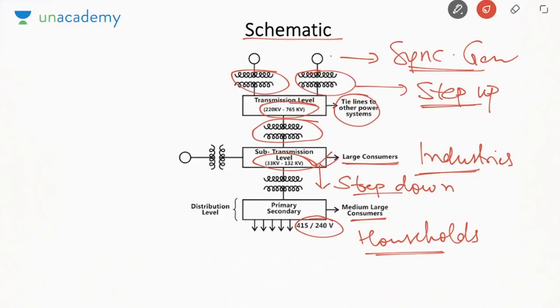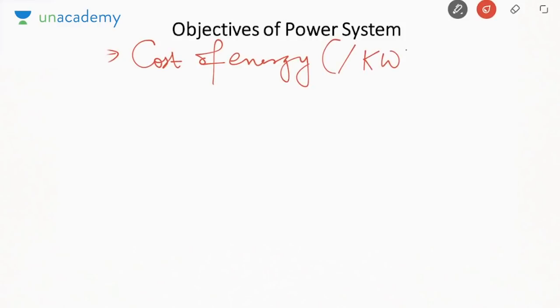Okay, so that is how a power system operates. First it will generate the power, then it will transmit the power, then it will distribute the power to different consumers. Now when we are designing a power system, there are certain objectives that must be met every time. The first and the most important objective is cost of energy. Cost of energy per kilowatt hour or per unit must be minimum.